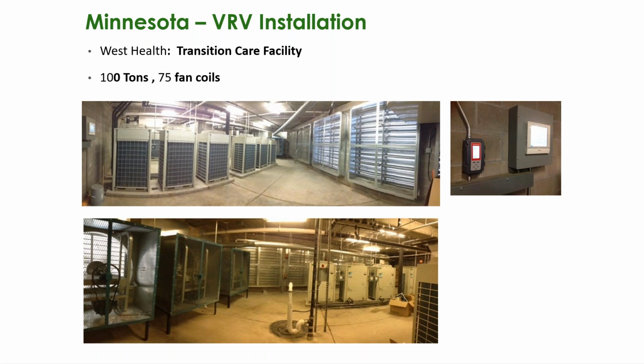And you can see in this scenario, they didn't do exactly what we showed in those images, where you're discharging through ductwork off of the condensing unit, because the piping and the ceiling height were prohibitive to that. So what they have instead here is the damper wall and then some large propeller fans blowing out on the other side. So they're achieving the same effect with large fans instead of using the fans off of the condenser itself to discharge out of the space.